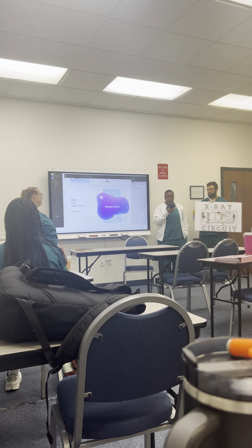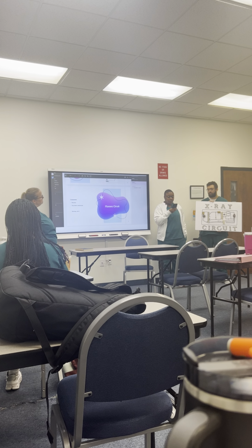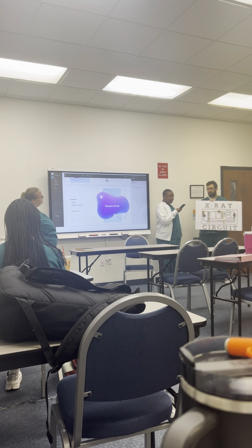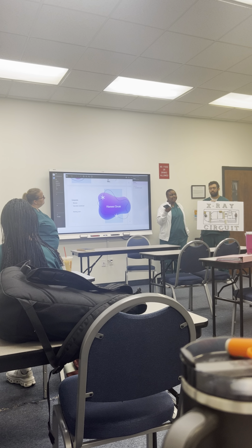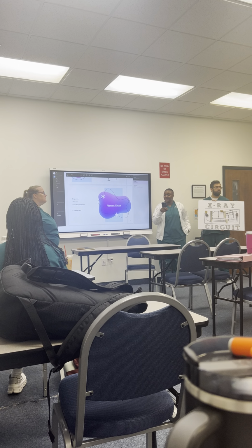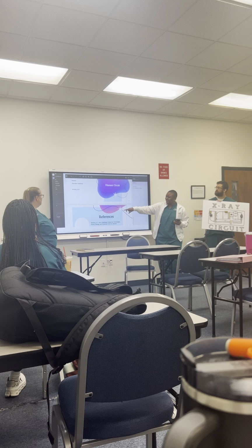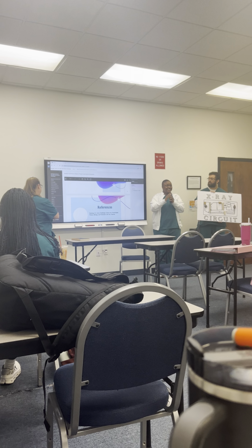If the step-down transformer fails, it could cause the X-ray tube to not receive the necessary voltage to heat up electrons, which would lead to no X-rays. Yeah, that's it. That's the X-rays.